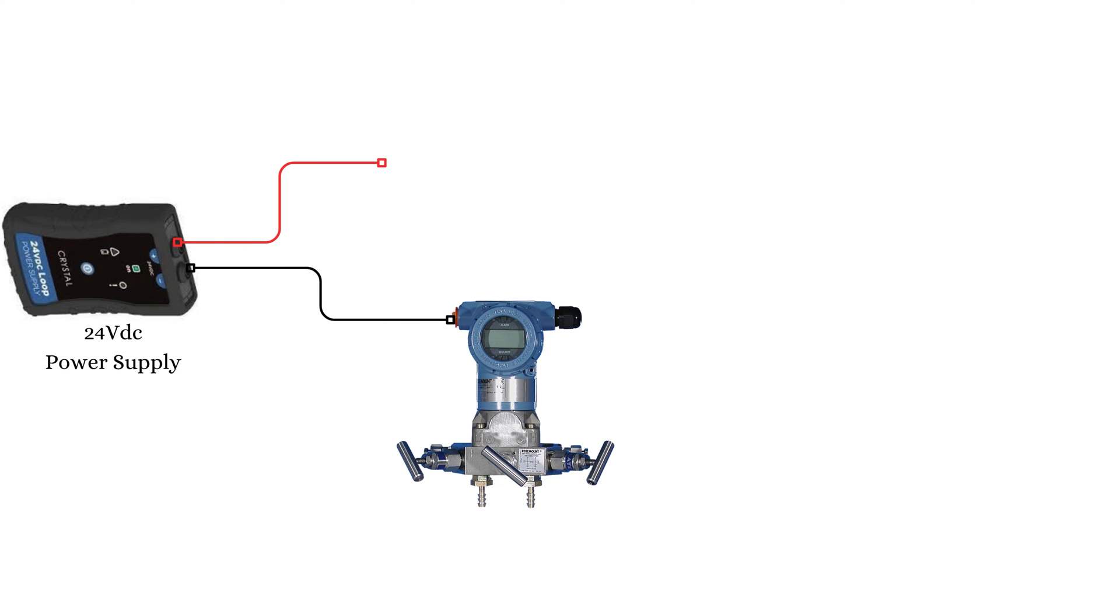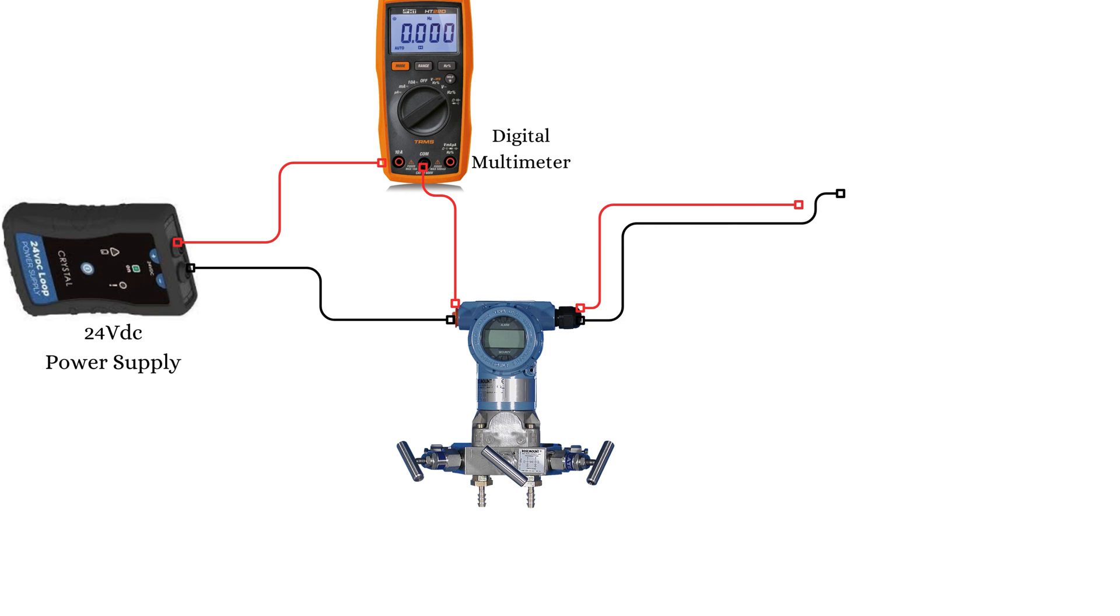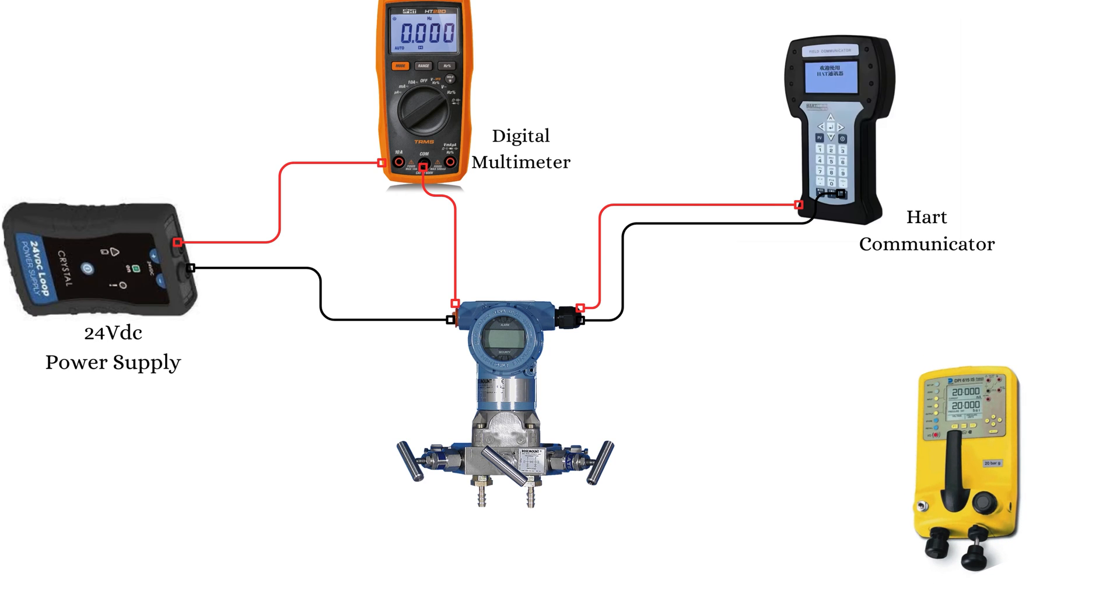Connect the power supply, the multimeter, and the DP flow transmitter in a series configuration. Make sure to connect the multimeter leads to the mA terminal and the common terminal. Now connect the DP transmitter to the pressure calibrator using the appropriate tubing.